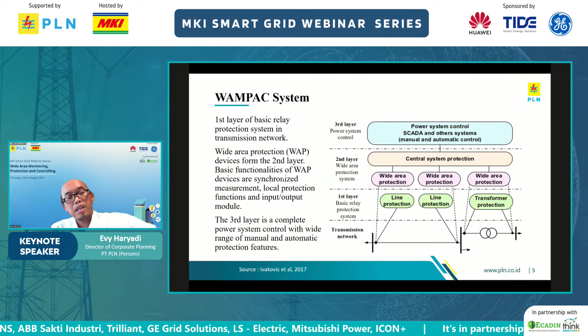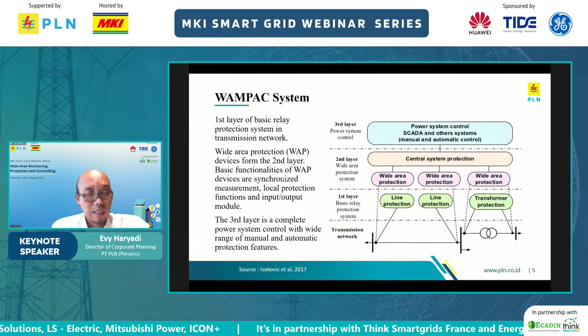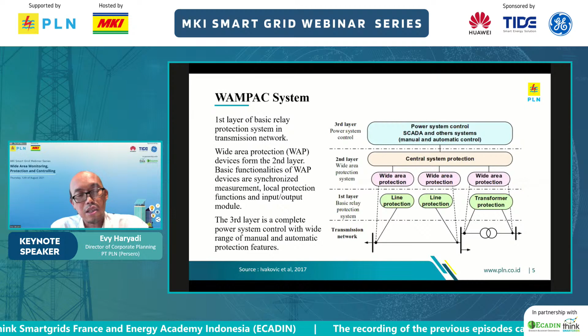Here we talk about the WAMPAC system, as shown in the figures. Line and transformer protection from the first layer is the basic relay protection system in the transmission network. Relay protection acts locally at the element level, such as in a substation, and usually covers just one element. Therefore, only a limited quantity of data is exchanged between different protection devices.